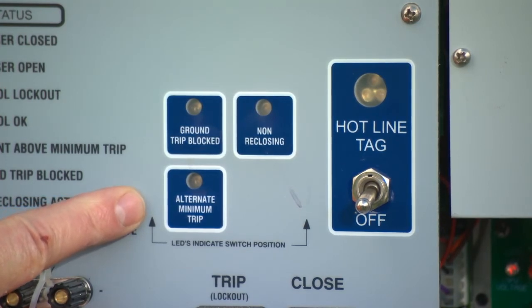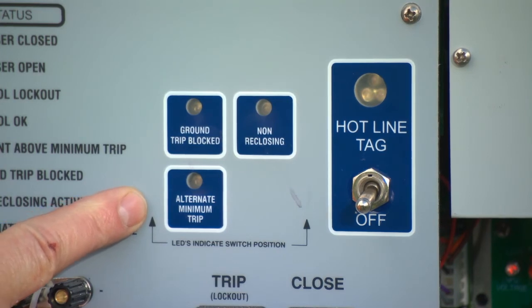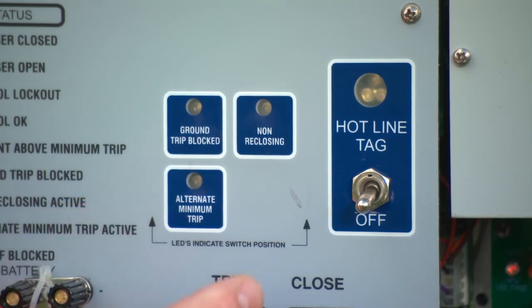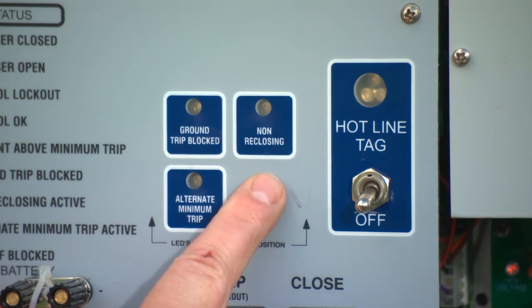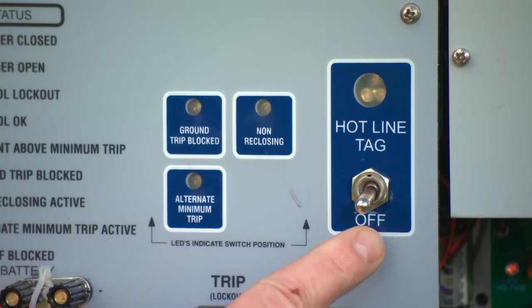This will apply a second set of settings into the control and make them active. You will notice this LED illuminate in addition to the status LED on the side. Applying the non-reclosing button will not allow the recloser to reclose. It is basically the same as a hold-off or hotline tag.